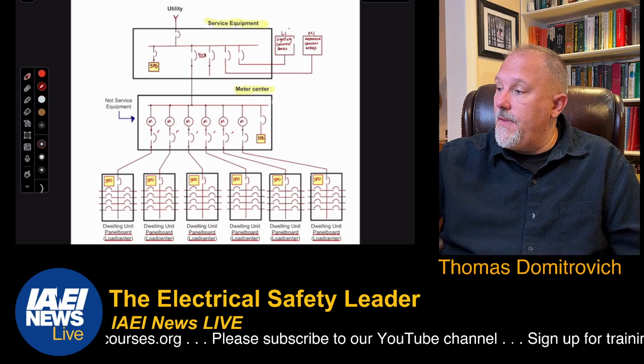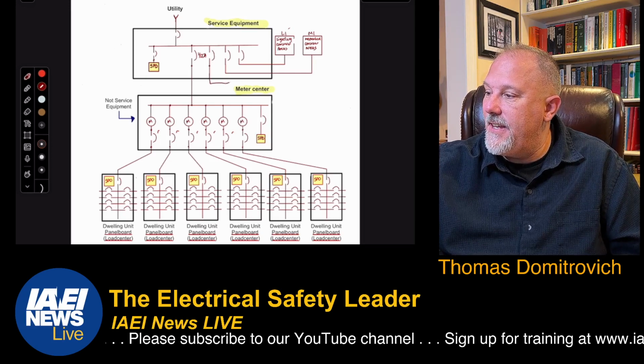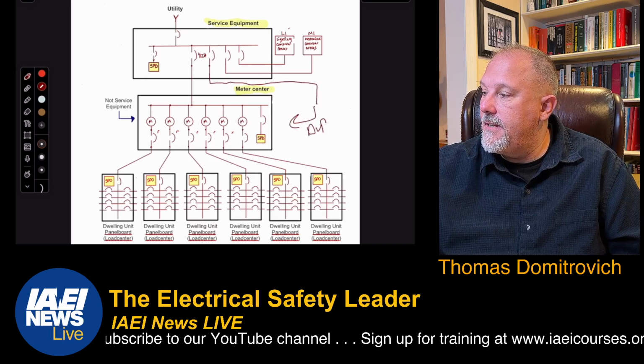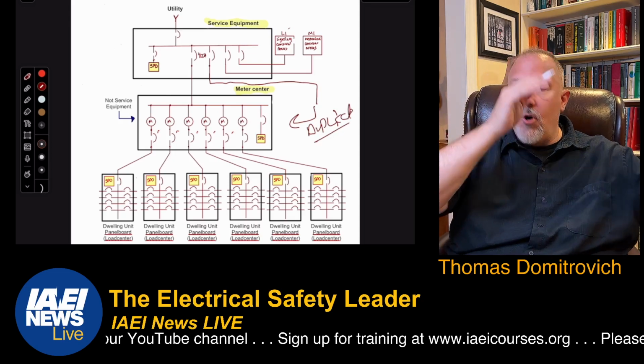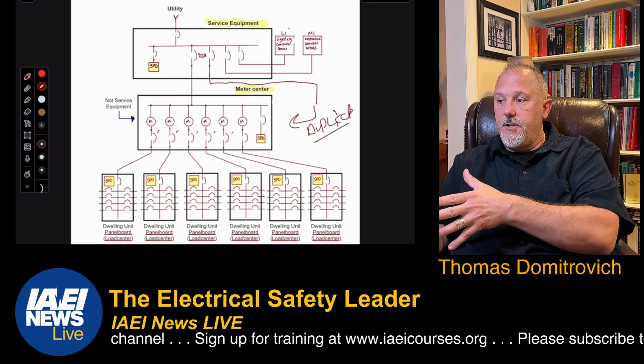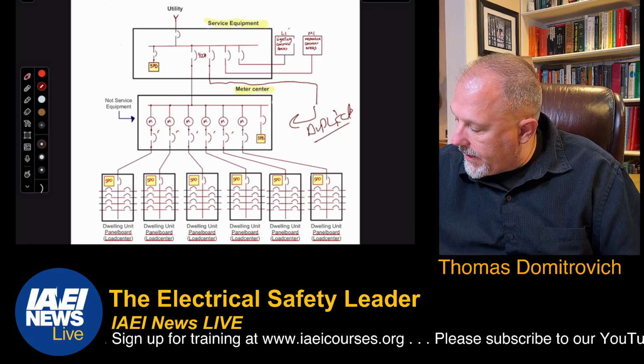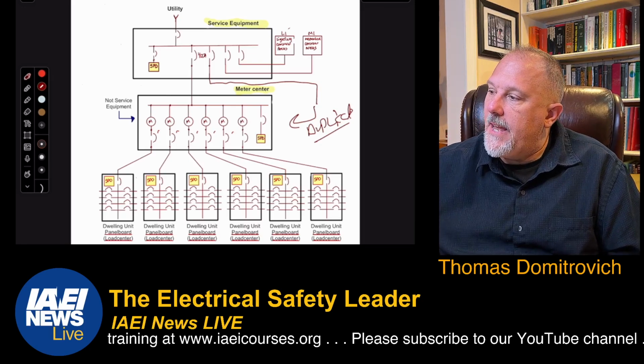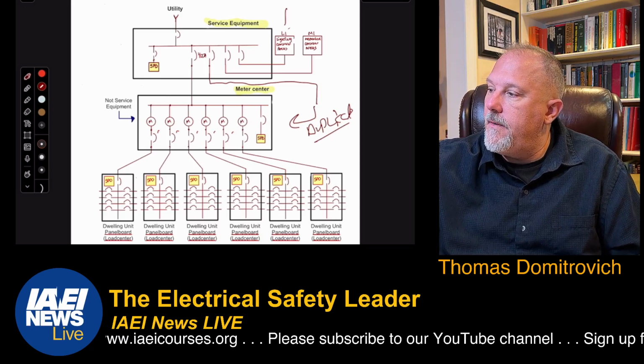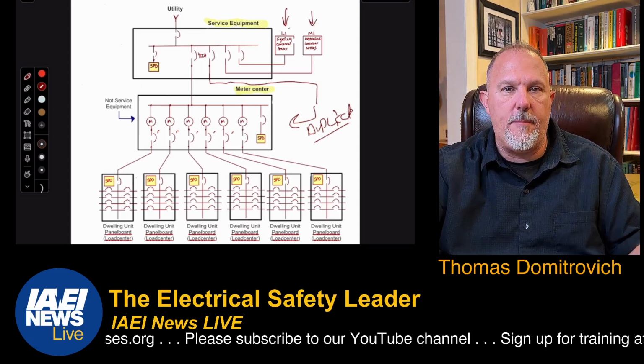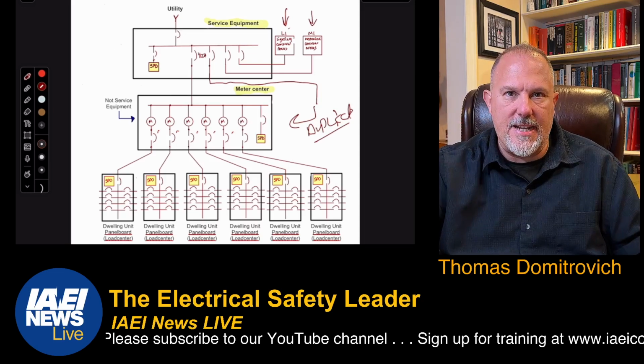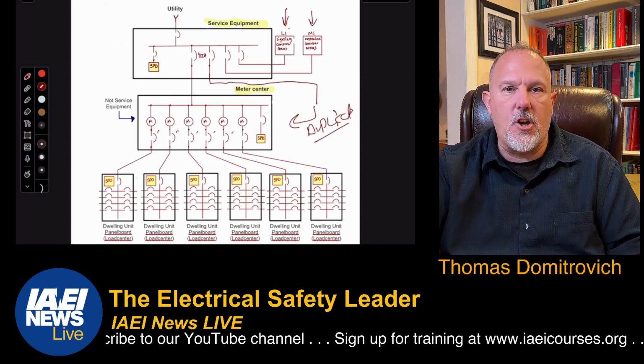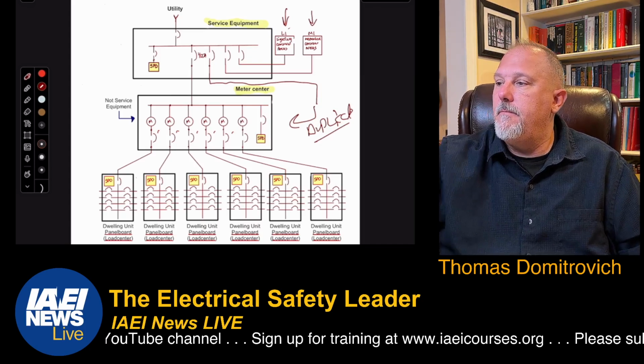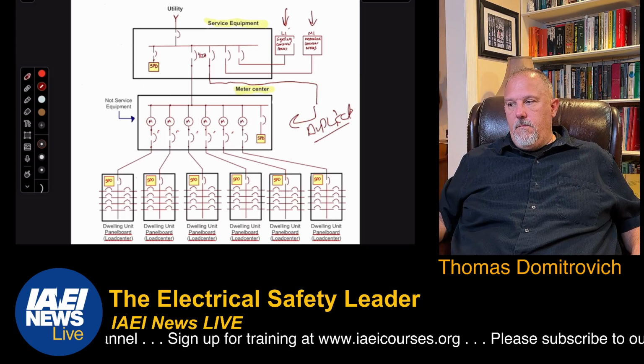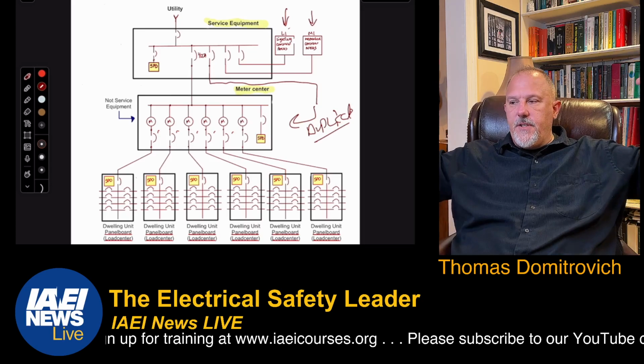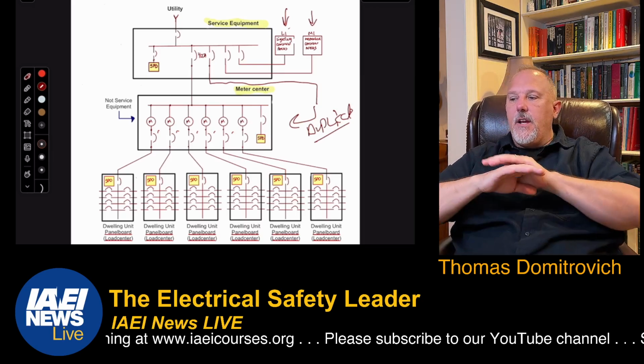Now, in the example that we had, I had this duplicated. So I had multiple meter centers feeding dwelling units. And I think there were like 400 and some dwelling units. And then off of the service equipment, you have a few panels that served common areas like hallways and outside lighting, maybe the laundry, any of the common areas, both from a lighting and from an equipment perspective. So you have your service equipment feeding multiple meter centers, feeding all of these dwelling units.